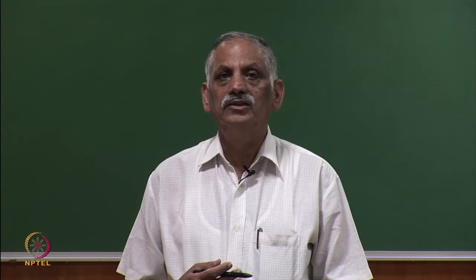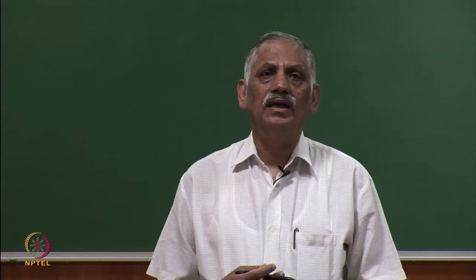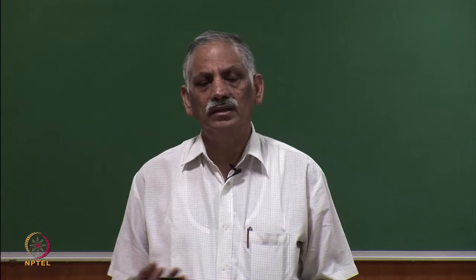These devices are known as custom power devices. For example, Distribution Static Compensator — D-STATCOM — can be used for reactive power compensation, negative sequence compensation, neutral current compensation, and even harmonic compensation. However, if harmonic compensation is added alongside the other three compensations, the device rating is affected because higher switching frequency devices must be selected.